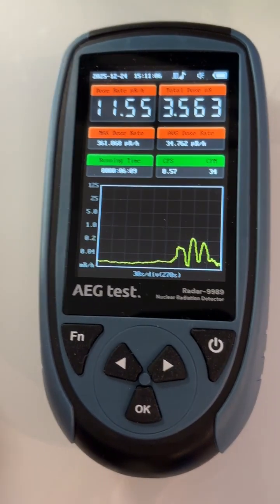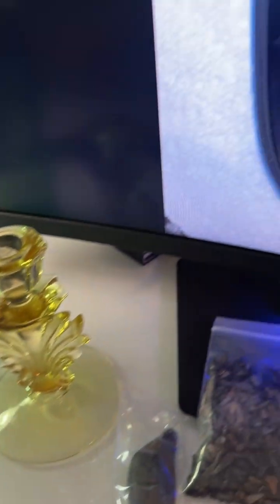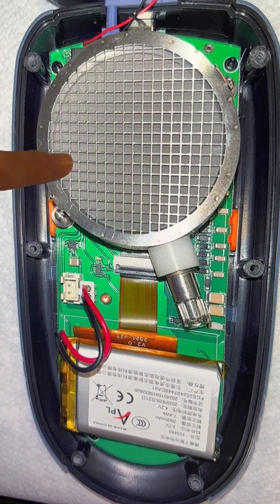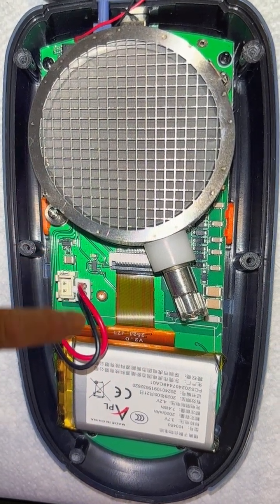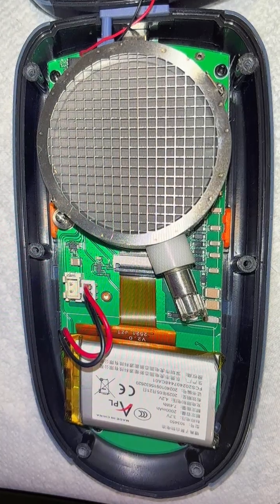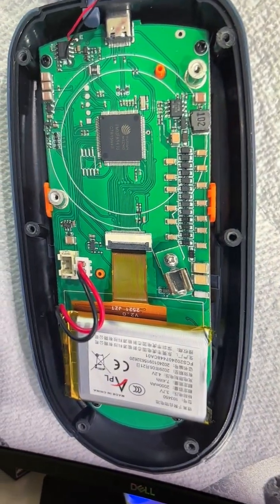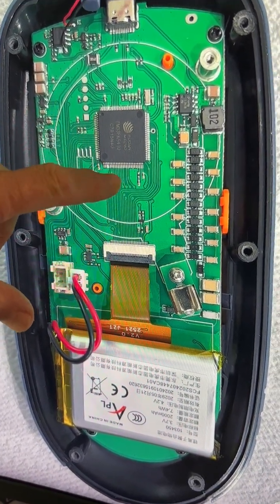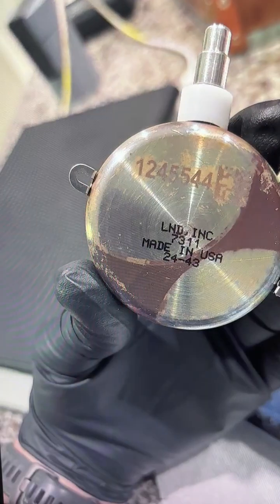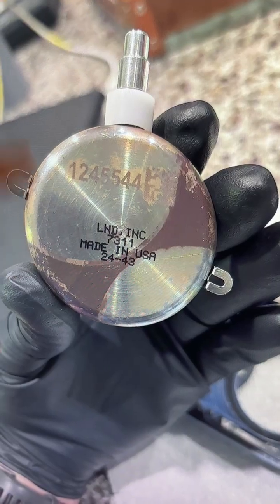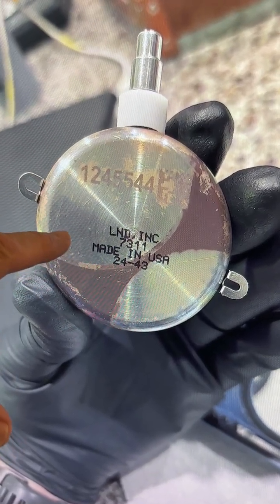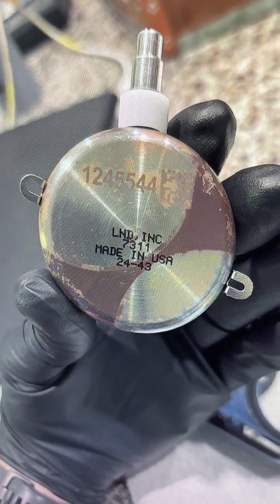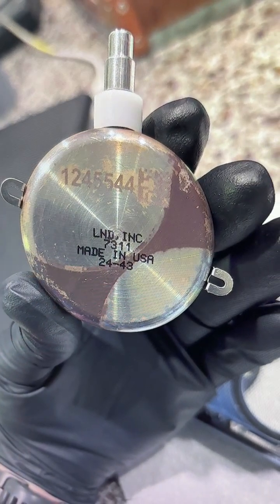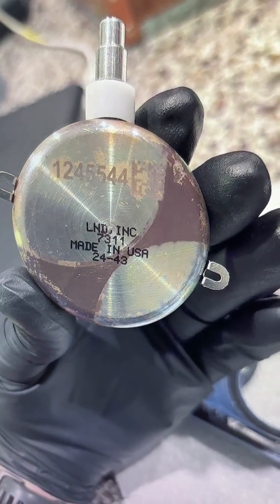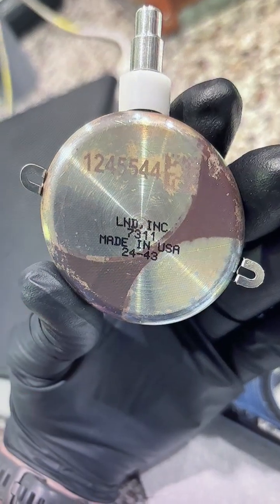I'm going to go over real quick the internals of the device. This basically is what it looks like when you open the cover. This is the LND pancake probe detector, the lithium ion 2000 mAh battery. And this is just a close-up of the side view of the pancake probe. This is with the probe removed, the LND detector removed, showing the circuitry. And this is me just verifying that it was and is actually an LND-7311 sensor, made in the USA. This is what gives this instrument its value. It's this quality detector. It really does. The instrument's built around a very good detector.